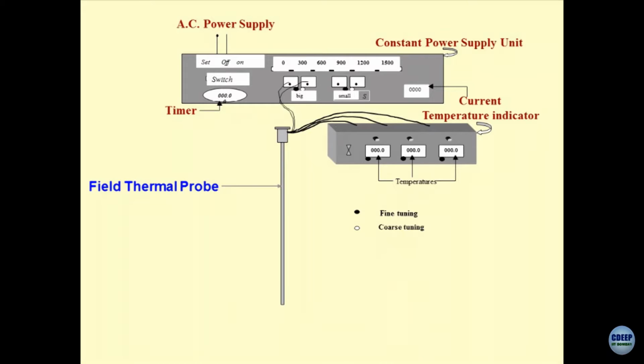What we did is we divided the entire probe into 3 sections, and in these 3 sections the temperature was monitored using 3 thermocouples. We call them the top, middle and bottom. The beauty of this system is that you can do thermal profiling of the ground up to 1 meter, and if you want to go deeper, you can cut a trench and do the first profiling for 1 meter, again 1 meter, and keep on doing it as long as the system permits.